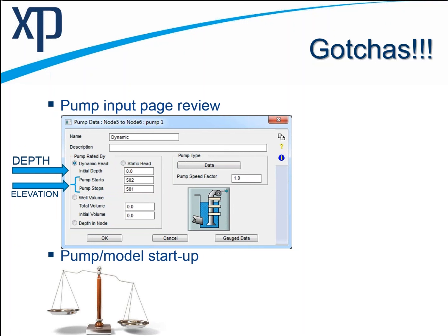Specific to kind of the pump modeling startup, there's a whole world of actually starting up a pump and shutting down a pump in reality. So this is a much smaller version. But if you're in the dynamic head world, you want to be careful that your upstream is not greater than your downstream. For me personally, it's confusing to me because I think of a pump pumping uphill. But of course, it's pumping to the downstream node. It's just probably a higher elevation. But recall, if the upstream node is higher than the downstream node, then you don't even really need a pump, right? Like, then downstream minus upstream is a negative number, and no matter what your pump curve looks like, it isn't going to run. So a lot of times I have people putting in their pumps and not quite getting it that correctly, and then hitting run and wondering why the pump never runs, even though the wet well is joyfully overflowing. So that's another issue you might have.